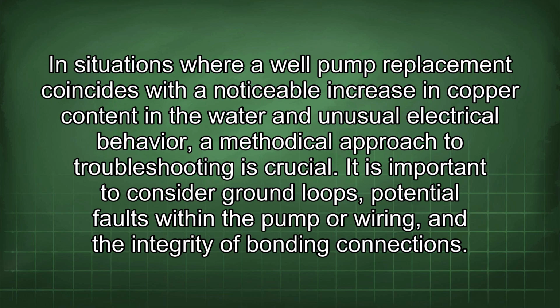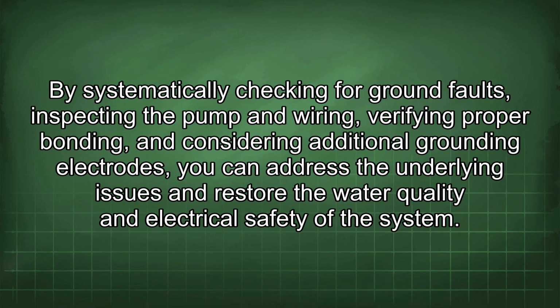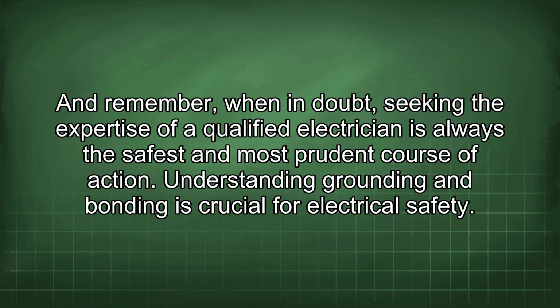It is important to consider ground loops, potential faults within the pump or wiring, and the integrity of bonding connections. By systematically checking for ground faults, inspecting the pump and wiring, verifying proper bonding, and considering additional grounding electrodes, you can address the underlying issues and restore the water quality and electrical safety of the system. And remember, when in doubt, seeking the expertise of a qualified electrician is always the safest and most prudent course of action. Understanding grounding and bonding is crucial for electrical safety.